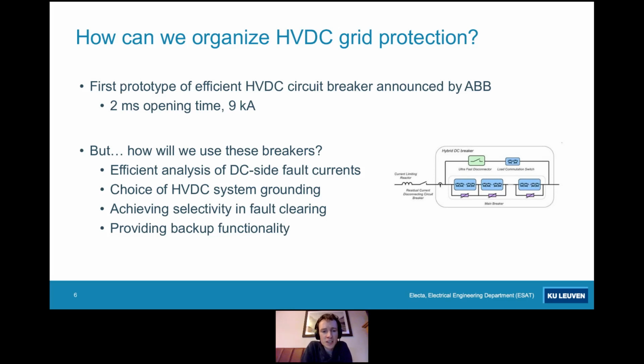And then also a large part of my PhD, I spent on algorithms that could achieve selectivity in fault clearing. So that could detect and identify faults in the sub-millisecond time range, and also to provide backup functionality in case a breaker fails, so that we still take corrective actions.